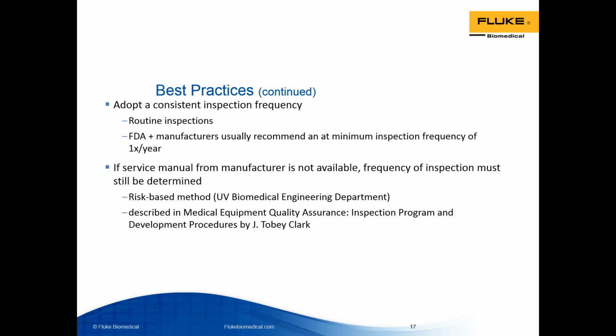If the service manual and the inspection procedure from the manufacturer are not available, the frequency of inspection must still be determined. So one method for determining how often a medical device should be tested is a risk-based method used by the University of Vermont, the biomedical engineering department there. And I'll show this on the next slide. But this risk-based method is described in the Medical Equipment Quality Assurance book, the Inspection Program and Development Procedures by J. Toby Clark.